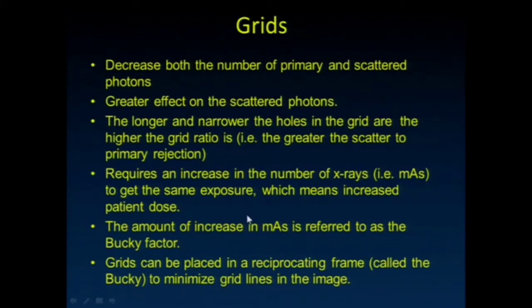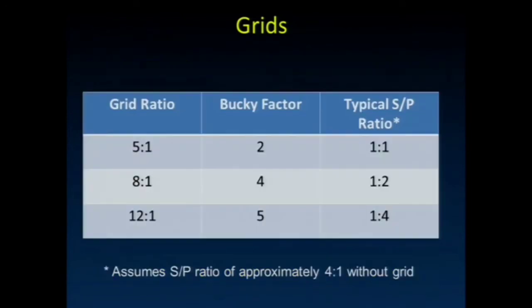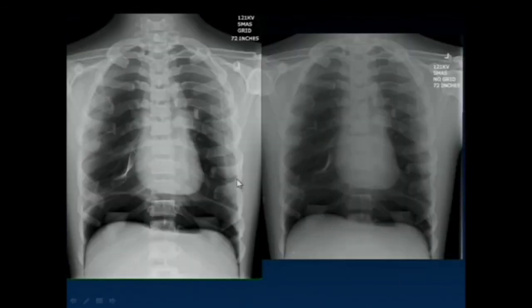We usually place the grids in a little bit of a reciprocating frame — they vibrate just a little bit, almost the diameter of the hole width, back and forth, so that you don't see the grid pattern on the radiograph. So here, for grid ratios of 5, 8, and 12, notice that the grid converts a 4 to 1 scatter to primary ratio to a 1 to 4 scatter to primary ratio. But the price paid is a need for a 5 times increase in dose to the patient. Here is a chest phantom done with the grid in place, and here's the same phantom done without the grid — everybody can see the reduction in contrast caused by all the additional scatter.